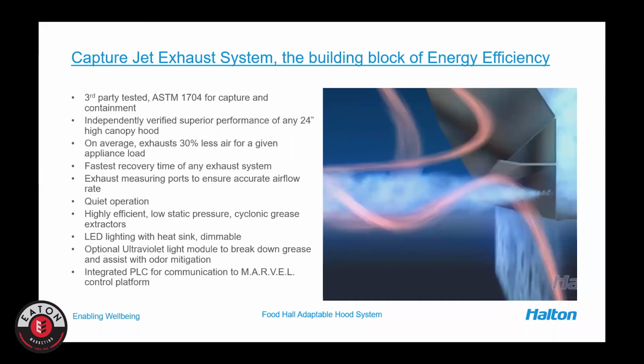Our hood is called Capture Jet. It's a high efficiency hood that allows us to exhaust typically about 25 to 30% less air than a standard canopy hood. It utilizes a patented jet technology that takes a very small amount of room air and induces it through a plenum at the perimeter of the hood. It allows us, via a low pressure or an induction effect at the front of the hood, to reduce the exhaust volumes by 25 to 30%, and in turn, reduce our supply volume.